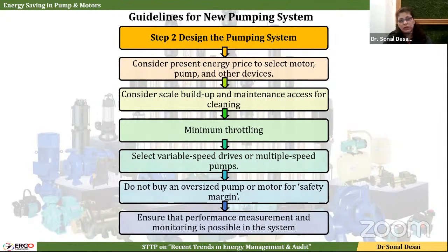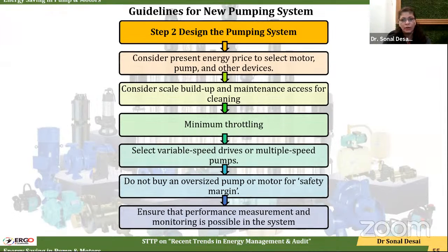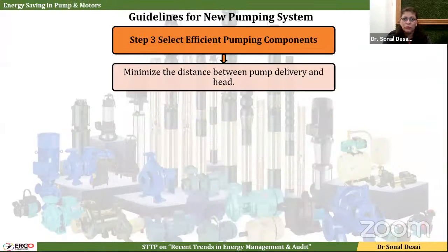Pump is something which you can always add on, because whenever a pumping system is there, there is always flexibility to add an extra pump in future. Adding a few feet of pipes and one more pump is always a less costly effort than running a big size pump continuously at a higher rate. And some more in the list.